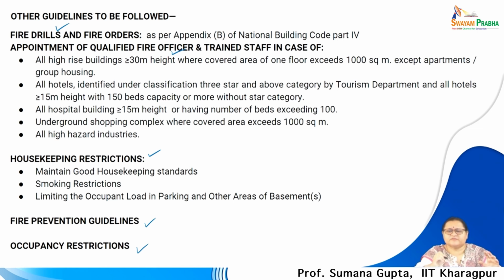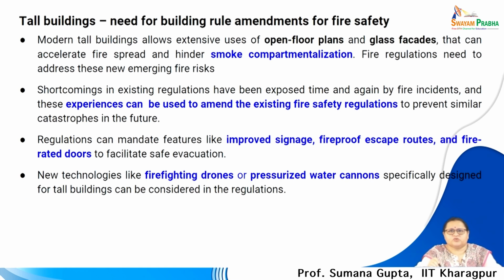So, consumable items, flammable items, cellulosic items, you cannot keep in the basement unattended, unaware. So, storage management has to be included very well in the design and the plan, so that storages are appropriately maintained and fire rated material is used. So, we need building rules amendments for fire safety in tall buildings particularly, or in high rise cases, which have to have smoke compartmentation enforced. Experiences can be used to amend the existing fire safety regulations. So, we need trained people or knowledgeable people who can bring in changes.